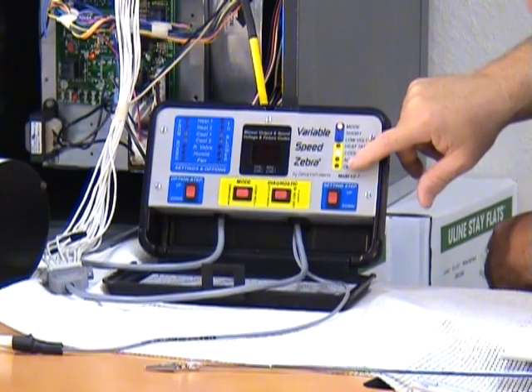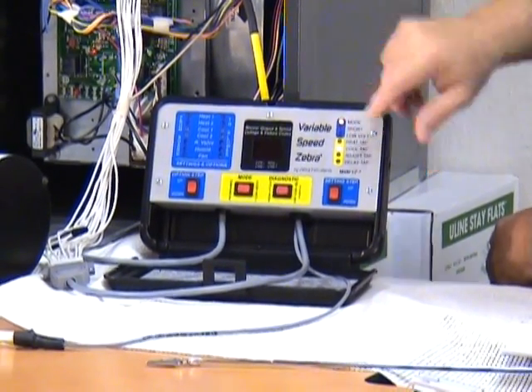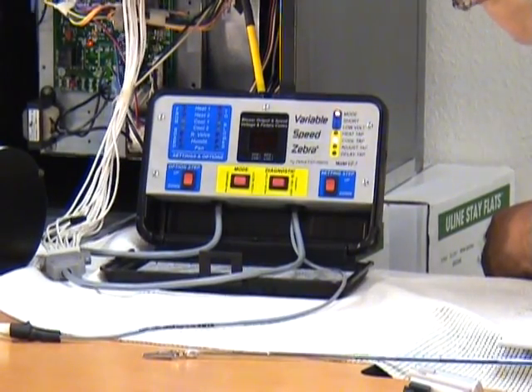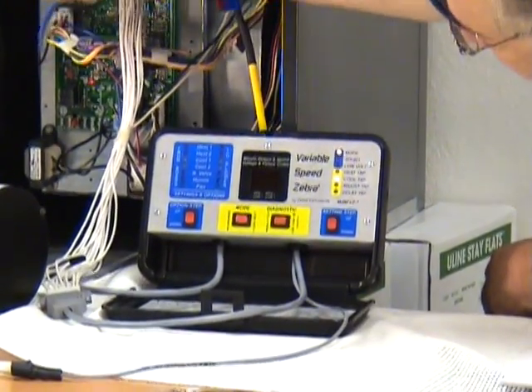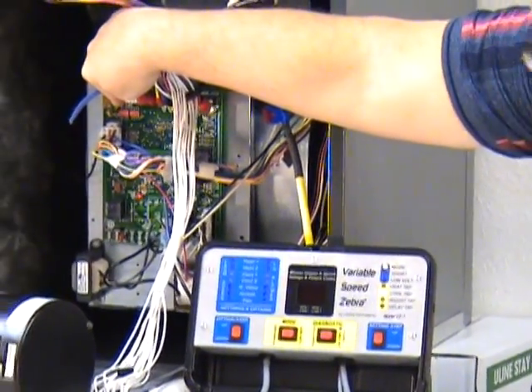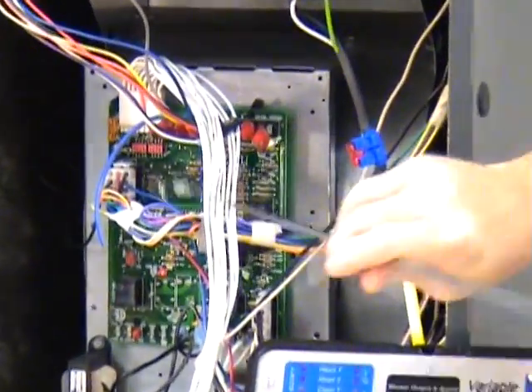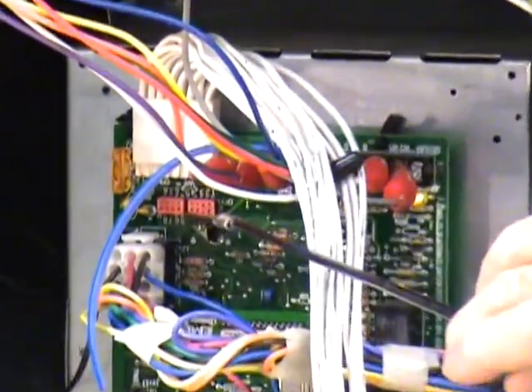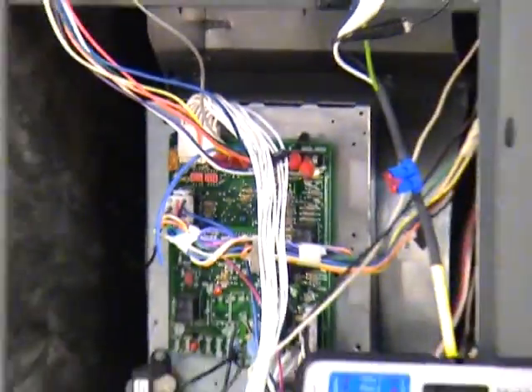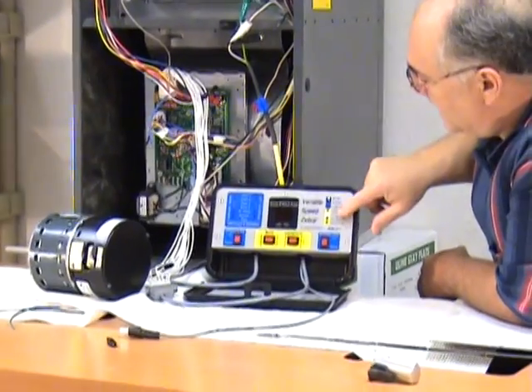Those are indications of the switch settings, the little dip switch settings on your circuit board. Go ahead and pan over there, Lisa, and let's take a look at that switch. Let me just put that in there. You see that switch right there? Those sets of dip switches, or sometimes little jumper settings where you place the jumpers on different pairs, those things set up the taps.